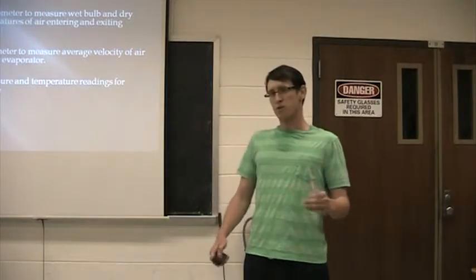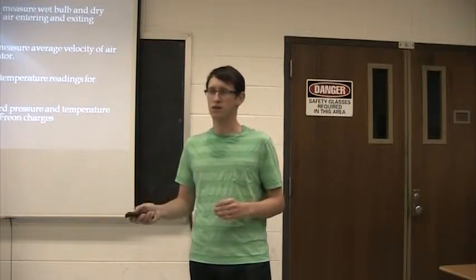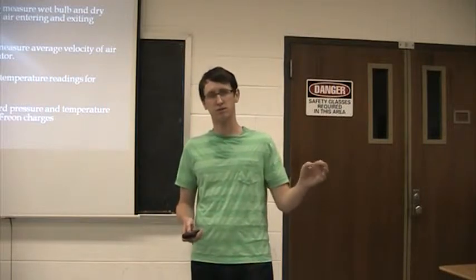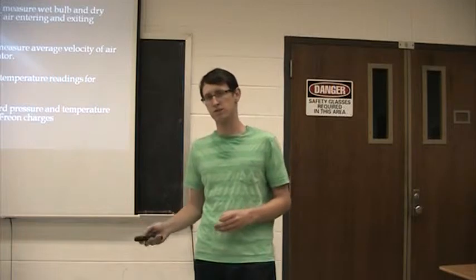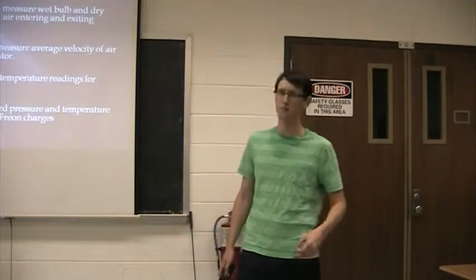Then, we're going to record the pressure and temperature readings for that case. And then, we're going to trade off between the two groups, draining the freon in half-pound increments. It's going to be a scale. That's going to be how you measure it. From 14 to 17 pounds in half-pound increments each time measuring temperature and pressure.